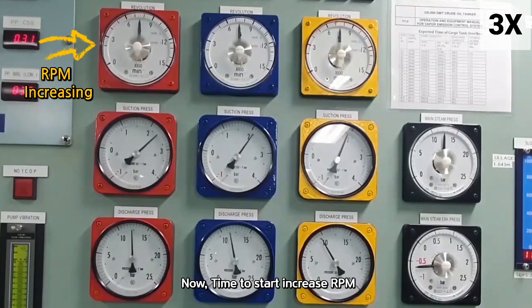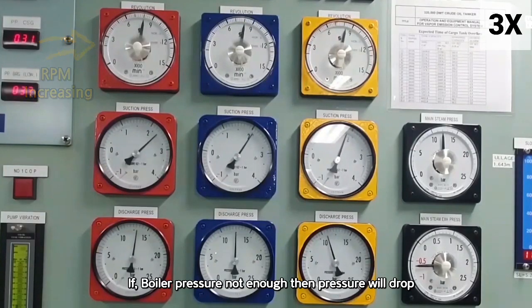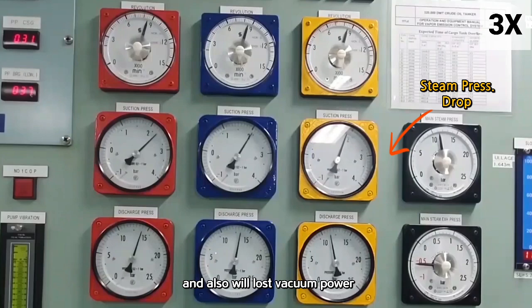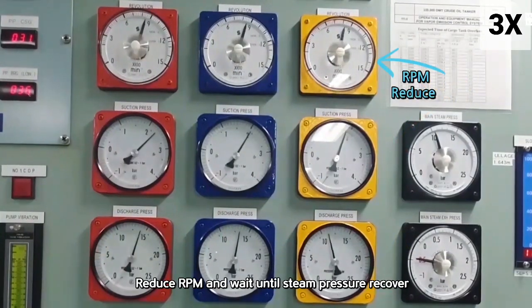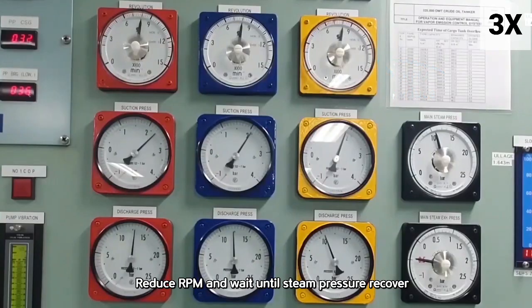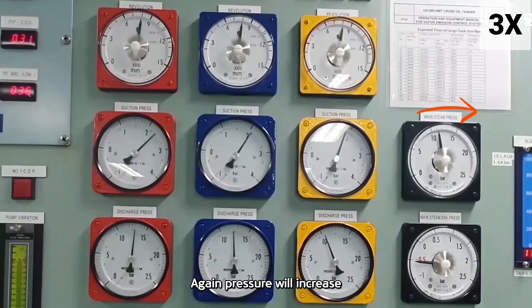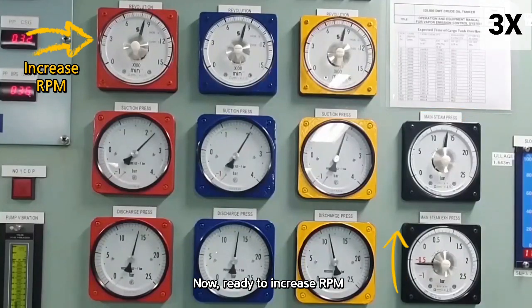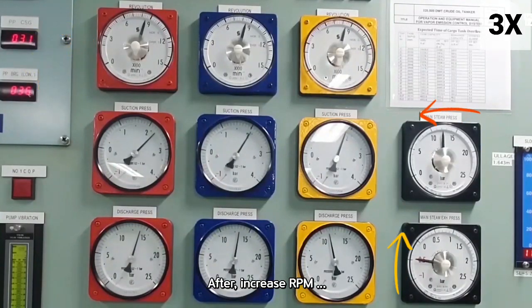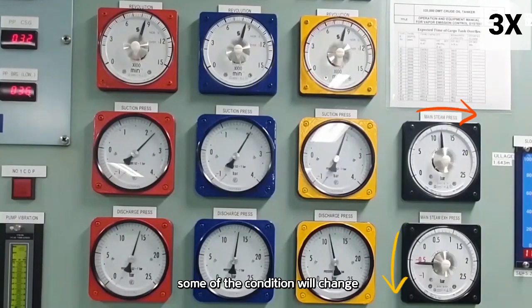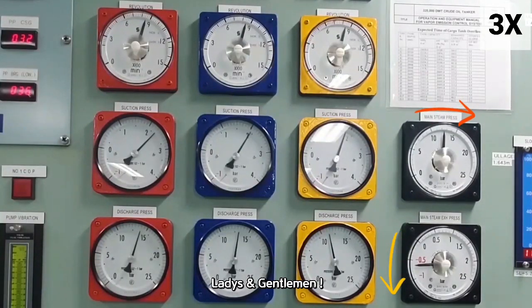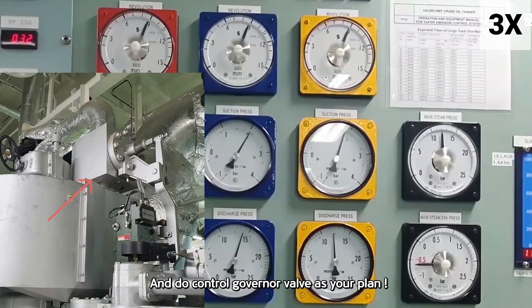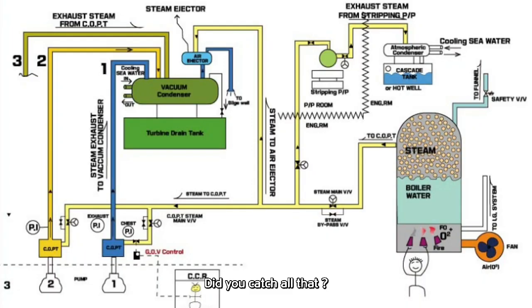Now, time to start increasing RPM. If boiler pressure is not enough, then pressure will drop, and we'll also lose vacuum power. Reduce RPM, and wait until steam pressure recovers. Once steam pressure recovers, pressure will increase again, and vacuum power will also increase. Now, ready to increase RPM. After increasing RPM, maybe you can see some of the conditions will change. Ladies and gentlemen, please keep monitoring both gauges and control the governor valve as you plan. Go ahead. Did you catch all that?